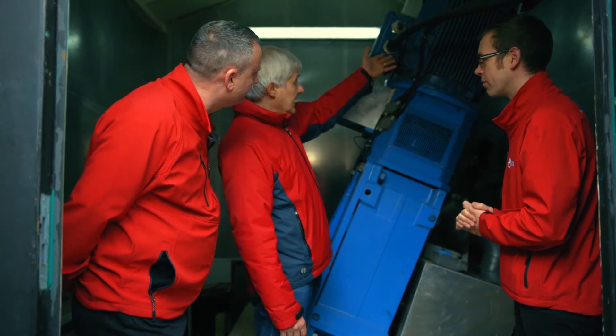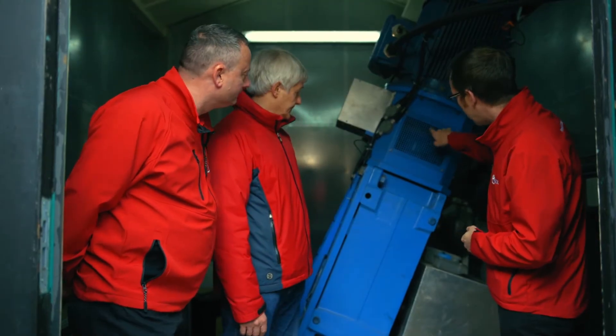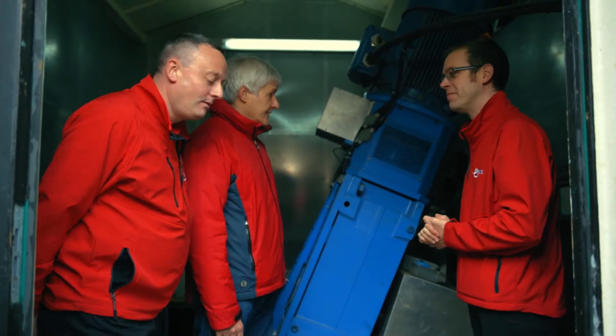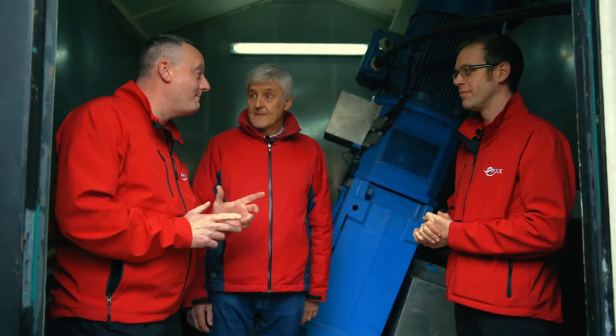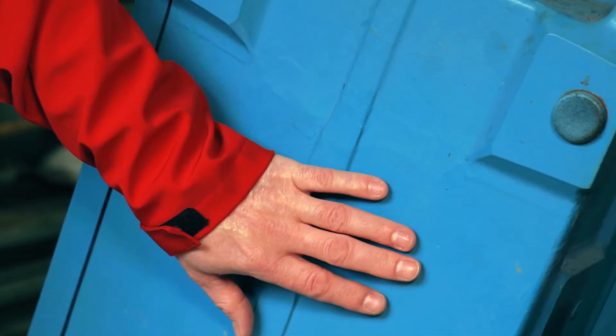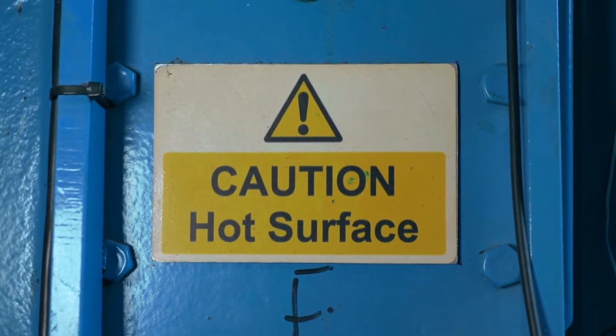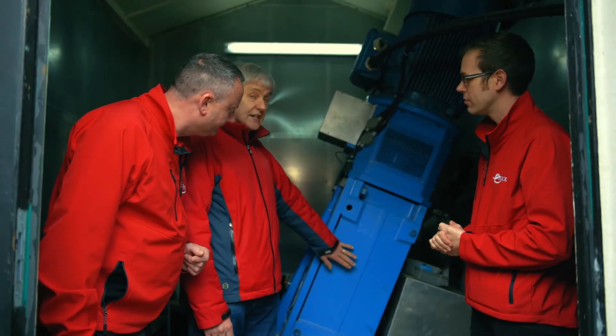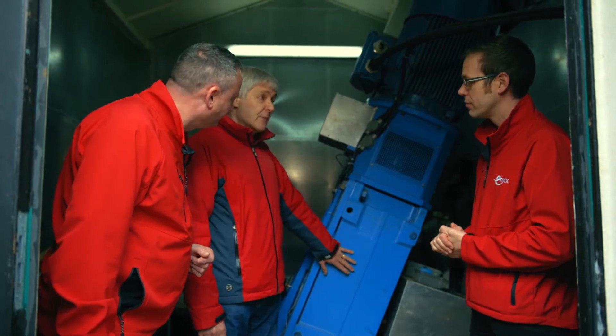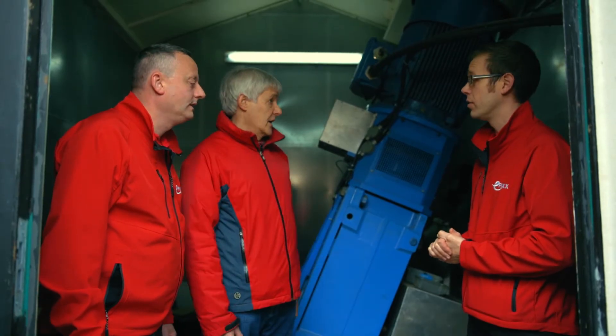It then heads off up through a brake into a conventional electric motor where we convert it into electricity and it goes out through this cable. If you look through that grill you can see that it is rotating really, really quickly — we're doing about 1,650 RPM at the moment. On a November day the ambient temperature in here is lovely and warm, but this gearbox is absolutely roasting hot. Is that another one of those losses we're incurring? It is absolutely yes. The temperature gets up to about 85 to 90 degrees and it's about four kilowatts — that's about 10% of our total losses.